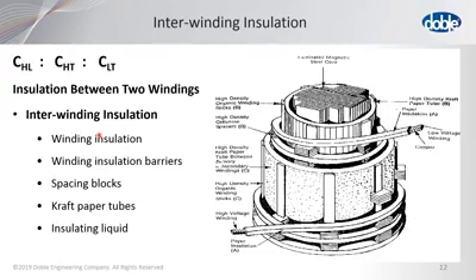Thank you. Should we still be performing DC insulation resistance tests on these transformers in addition to power factor testing? What would your test voltage be for a 345 kV transformer? Okay, for insulation resistance testing, the recommendation that Doble would make would be that they can be performed.